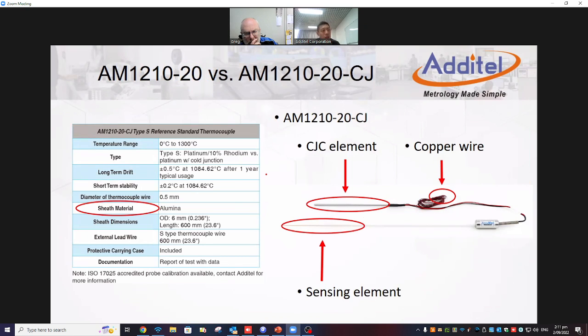If the customer uses this one, they have to make sure the readout they have for this reference probe does have the internal temperature compensation. Because this is thermocouple testing, they have to make sure the readout they use for the 1210 probe has the internal compensation.